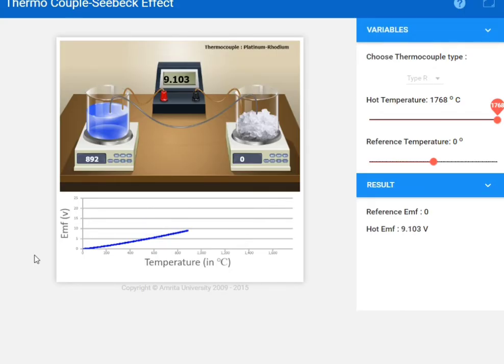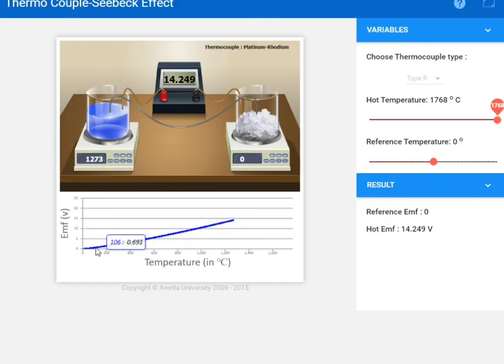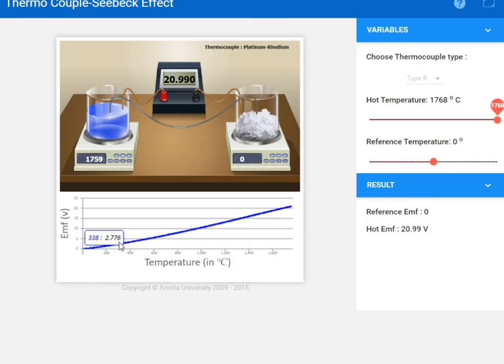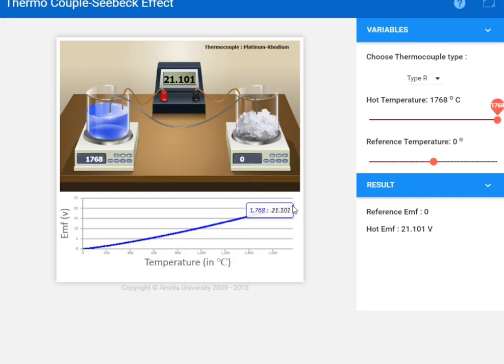Now note down the readings. At the first point, the temperature is 106°C and the EMF is 0.693. Stay at another point — the temperature is 205 and the EMF is 1.5313. At the last point, the temperature is approximately 1768°C and the EMF is 21.101. In this way you can easily get readings from the simulation.